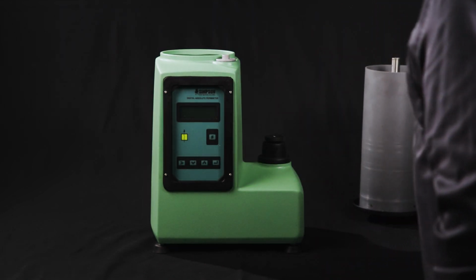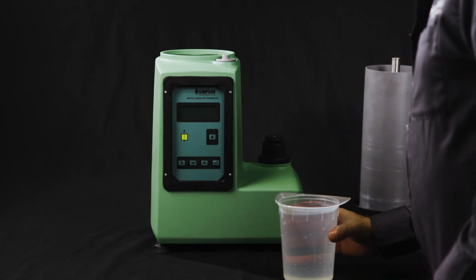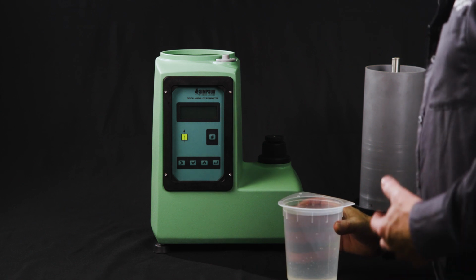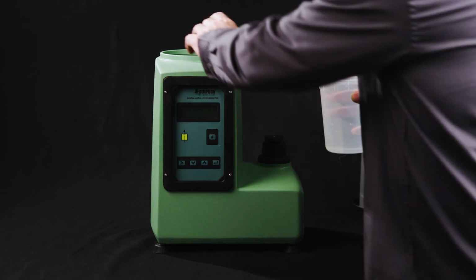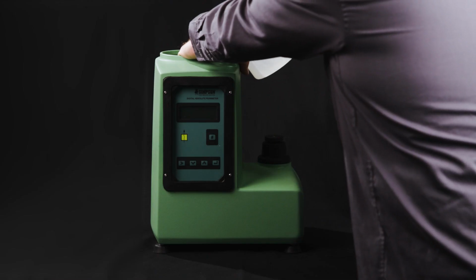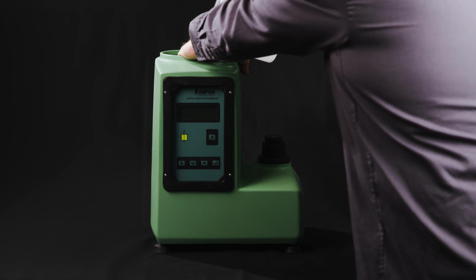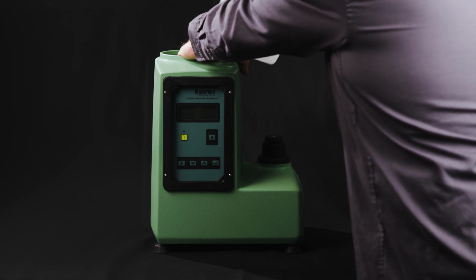Then we are going to add our water and antifreeze solution into the machine. So the first thing we need to do is have something to plug up the hole up here, and we're going to add the water. Internal to the machine there is a sensor, and we are going to add this mixture up to that sensor or to the prescribed amount of water that's on the calibration certificate.